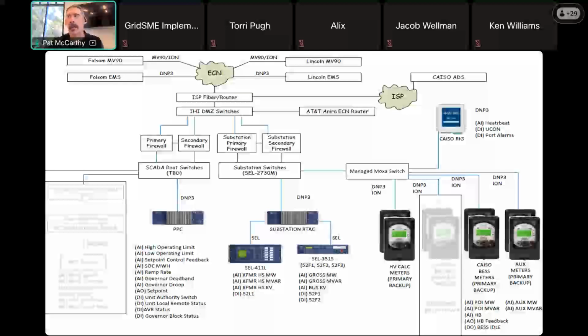Basically, the CAISO inspector is going to put a test set on, let's just say, your primary and backup meter for the PV, the thing I have grayed out there. They're going to inject, let's just say, 100 megawatts. CAISO will see that 100 megawatts through the rig in real-time telemetry. And then that 100 megawatts needs to also find its way into the revenue registers that will be brought into CAISO's EDAS team through that MV90 system.